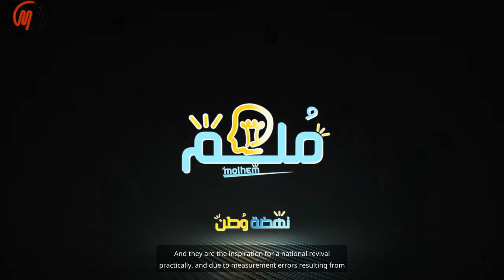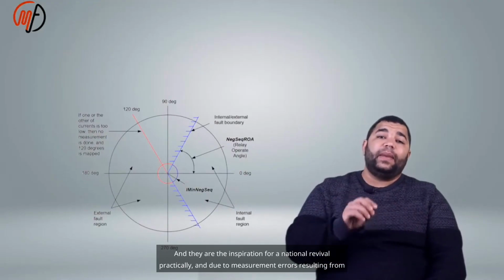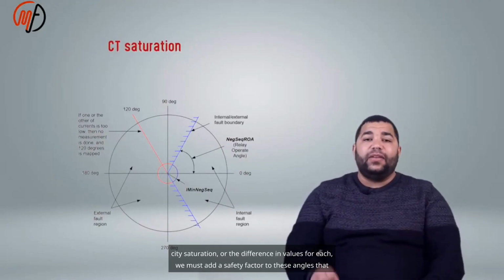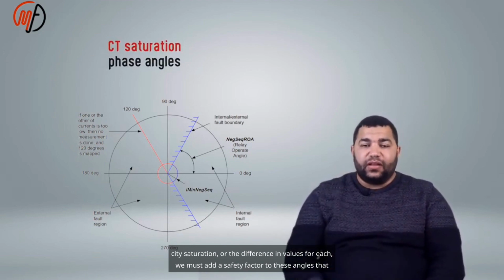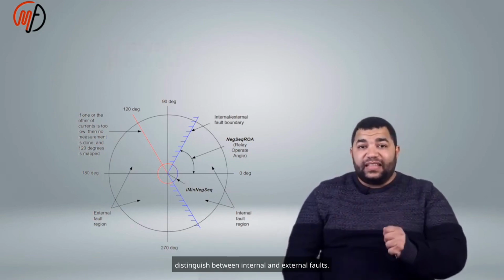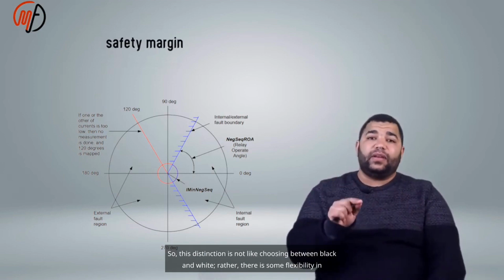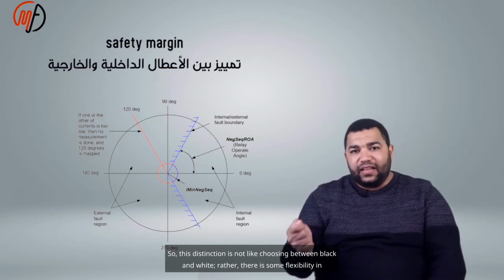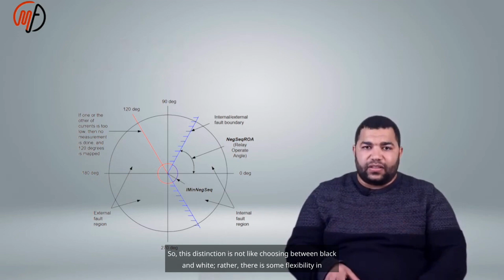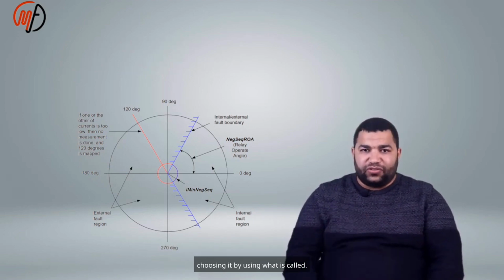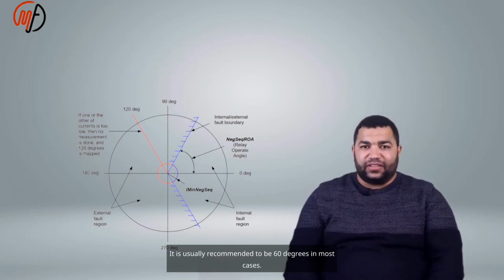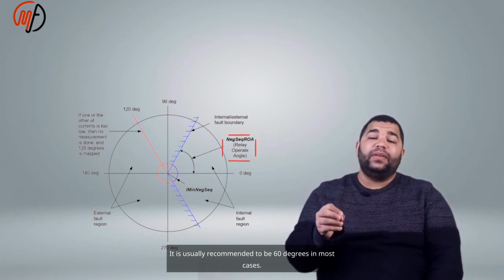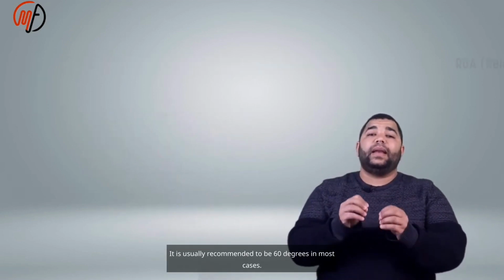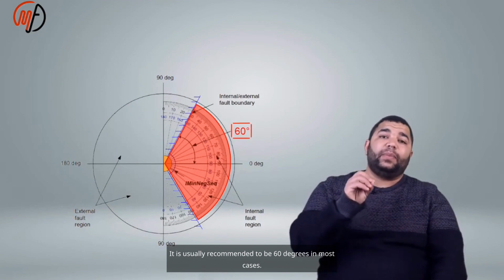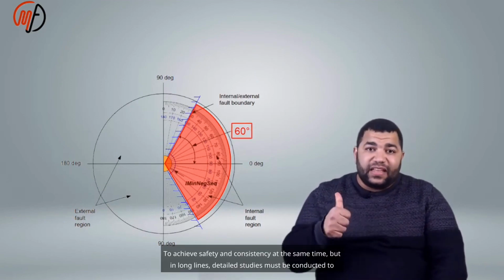Due to measurement errors resulting from CT saturation or the difference in values at each end, we must add a safety factor to these angles that distinguish between internal and external faults. So this distinction is not like choosing between black and white. Rather, there is some flexibility in choosing it by using what is called the angle setting, and it is usually recommended to be 60 degrees in most cases to achieve safety and consistency at the same time.